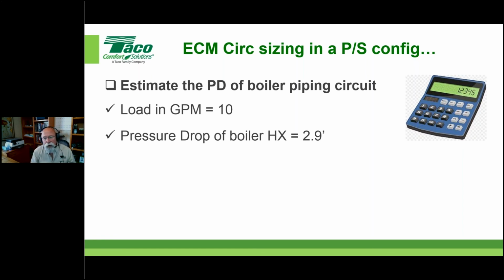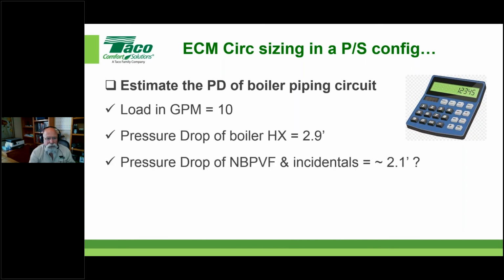Okay, always try to look it up if you can get somewhere online. Try to figure out what it is. But these very popular fire tube designs are much lower pressure drop. They're just buckets of water that we're pumping water through. There's not a lot of resistance. And again, a lot of these manuals, if it has to be from somebody else that has a similar one, you could probably use that. In this case, I'm just under 3 foot of head.